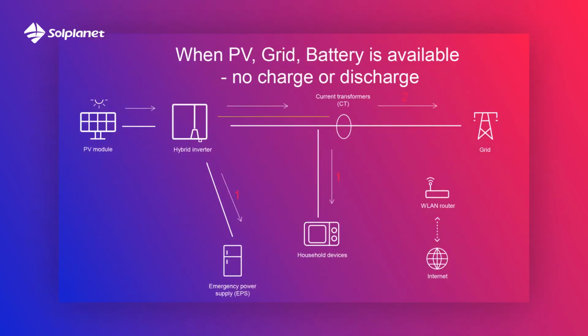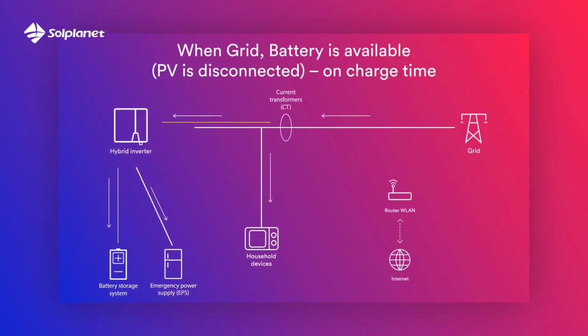If we now set no charge or discharge battery. In the period of no charge or discharge battery, the solar power supplies loads as first priority and the excess energy goes to the grid. When grid and battery are available, PV is disconnected or it is night.